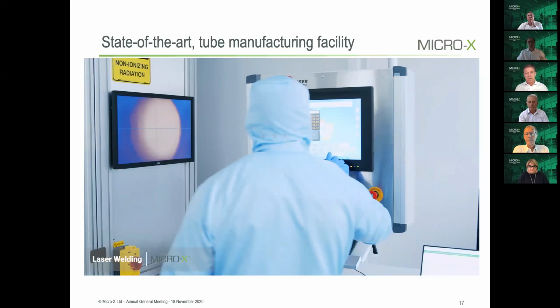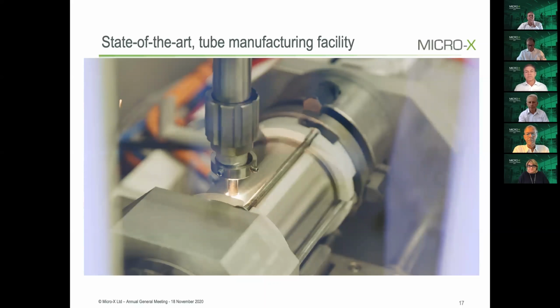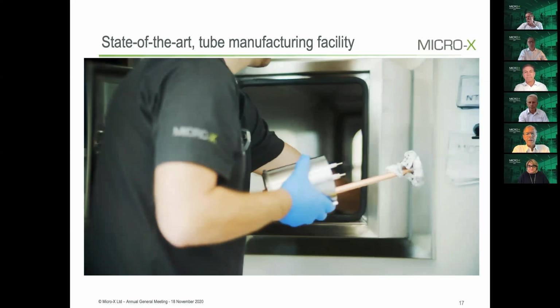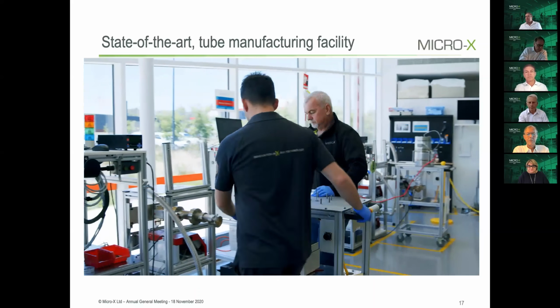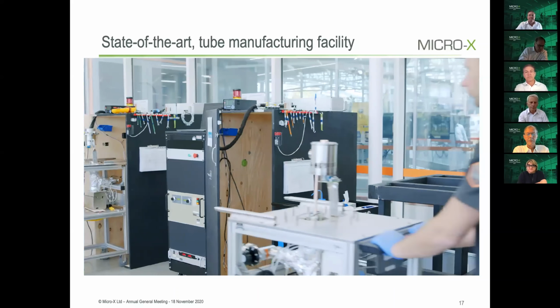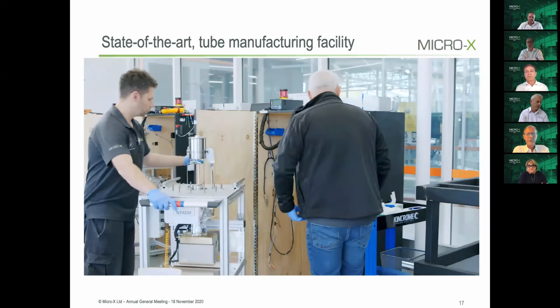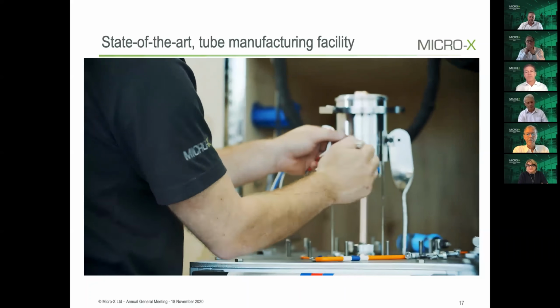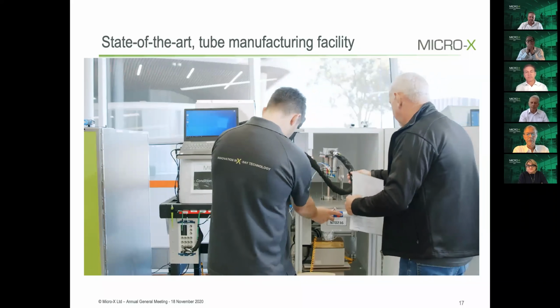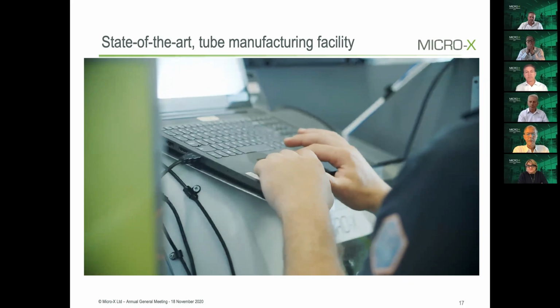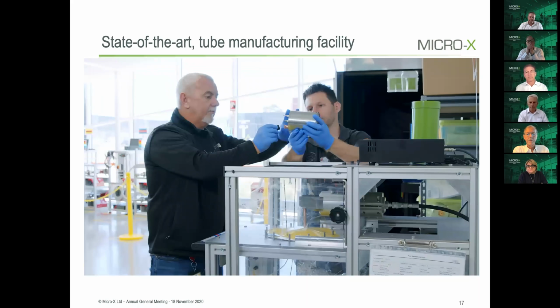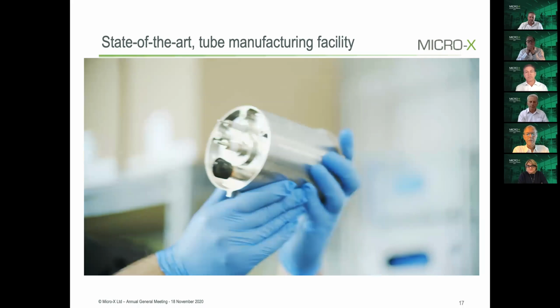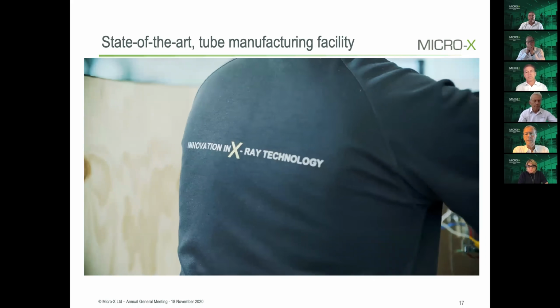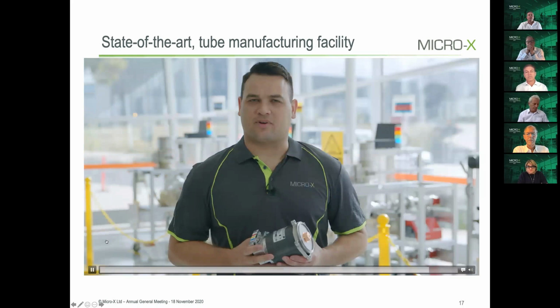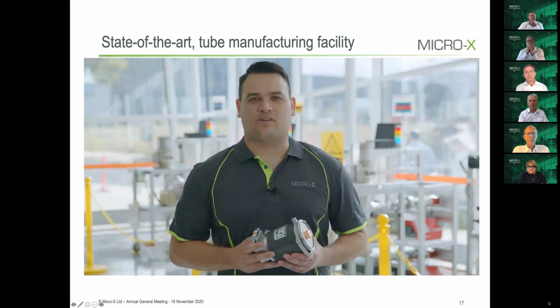It is a clean welding process performed in a clean room. The tube is then heated under vacuum to reach an ultra-high vacuum level that is equivalent to space. After the ultra-high vacuum is achieved, the tube goes through a number of processing steps to stabilize for high voltage. Our tiny tubes operate at 120,000 volts, which is very high for such a small volume. The tubes are then pinched off with a cold seam weld to maintain the vacuum in. The final step is end-of-line testing to ensure the tube performs as required and is ready for assembly into our products. And there you have it. That's how we manufacture our CNT tubes using a number of Industry 4.0 advances and our state-of-the-art tube manufacturing facility.